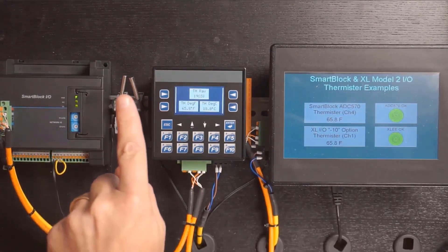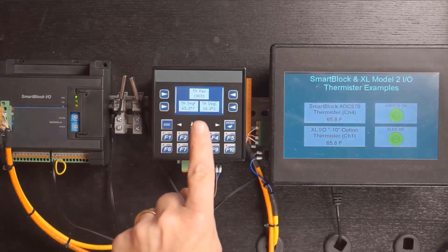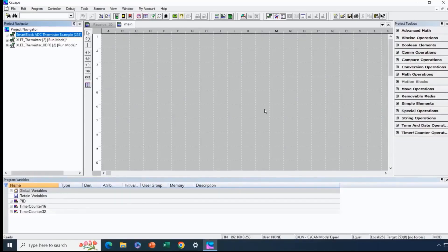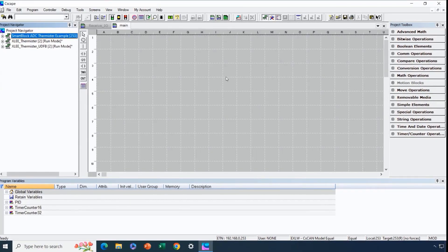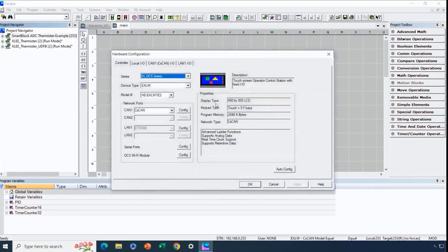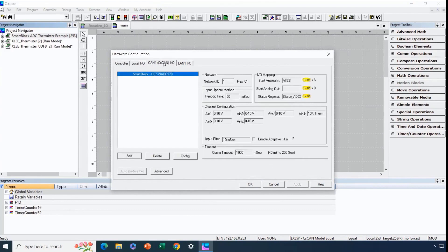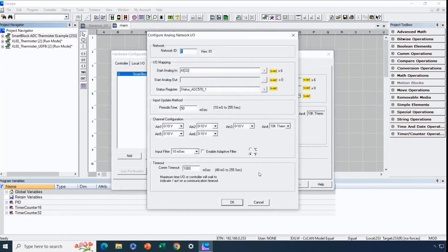Now we'll look at C-Scape. We'll start in the EXLW program and look at the configuration for the smart block. We go into hardware configuration and then to the CAN-IO tab, because smart block is a CAN-IO family. We've already added this ADC570 6-channel analog input module, so we'll double-click and see how it's configured. It's been assigned a network ID of 1, and we've assigned the starting real-world analog input register as AI32 as an array. Because we're using variable-based advanced ladder, it uses arrays as the real-world analog input values as variables.